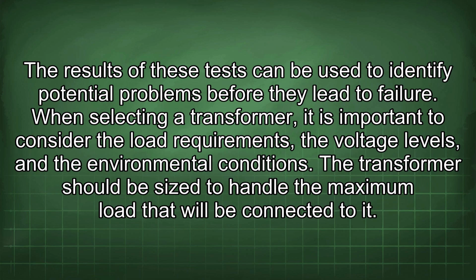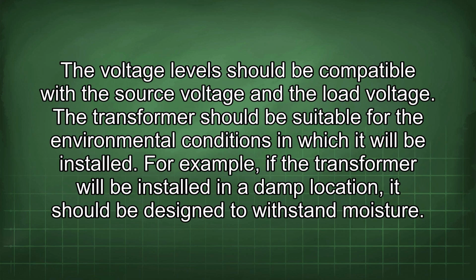When selecting a transformer, it is important to consider the load requirements, the voltage levels, and the environmental conditions. The transformer should be sized to handle the maximum load that will be connected to it. The voltage level should be compatible with the source voltage and the load voltage. The transformer should be suitable for the environmental conditions in which it will be installed. For example, if the transformer will be installed in a damp location, it should be designed to withstand moisture.